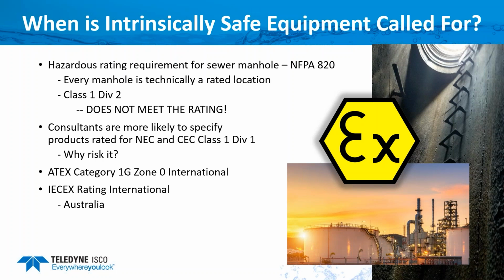Now note the EX symbol in yellow. It is recognized as the ATEX rated Zone 0. ATEX is an area marked as an explosive atmosphere or combustible gas, which could be dust clouds or mist, similar to the Class 1 Division 1. Now, ATEX is the acronym for Atmosphères Explosibles. It's a European Union standard for intrinsically safe products. The ATEX rating is a technical standard developed to minimize the risk of explosion caused by electrical or non-electrical equipment, such as flow meters and sensors in wastewater treatment.